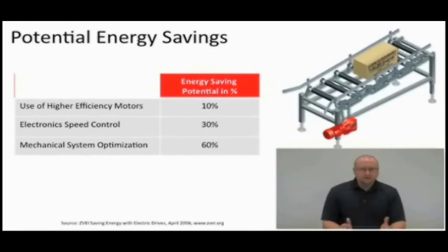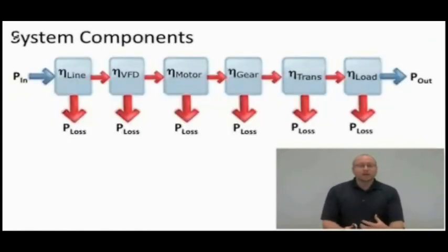Every system has different components. We've been talking about that for a couple minutes. You have your input power, your variable frequency drive, your motor, your gearbox, your transmission element, and then you have your load or the application that you're trying to move. Each individual component has losses. Nothing is 100% efficient, and definitely nothing is greater than 100% efficient. Einstein kind of proved that that's impossible.